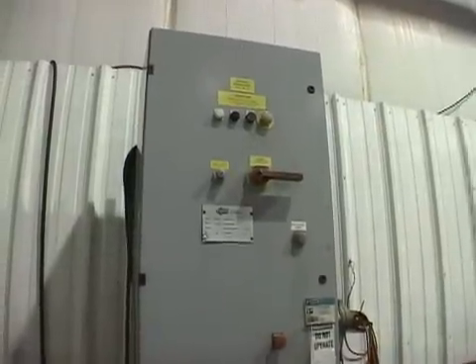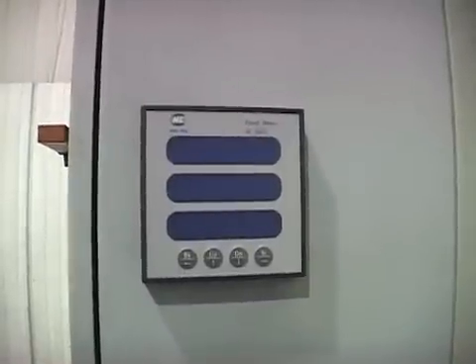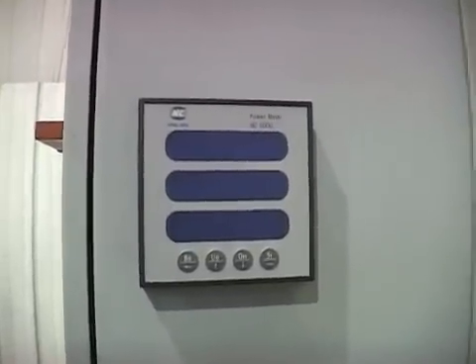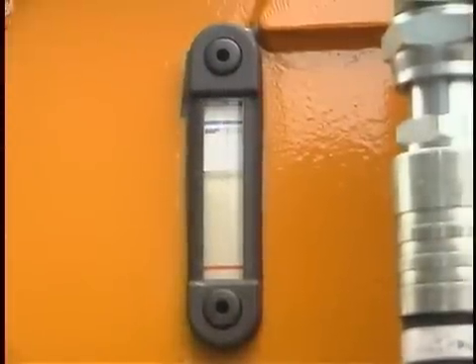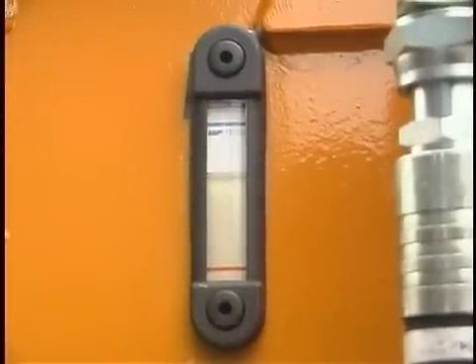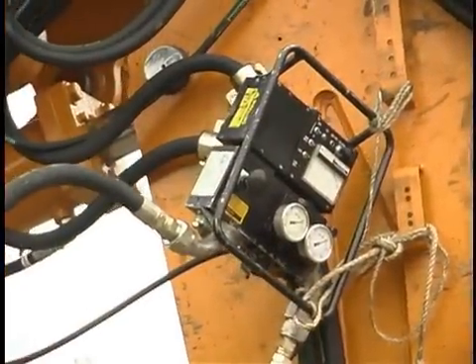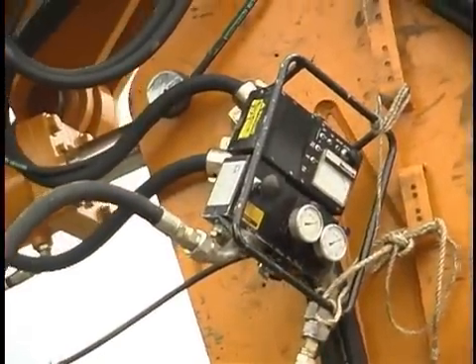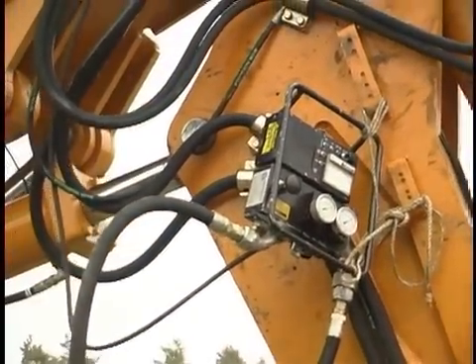Next, the motor voltage is verified from the specifications on the design plan. The oil level is checked and the oil type is documented. The power pack details are then documented to include flow and pressure settings.